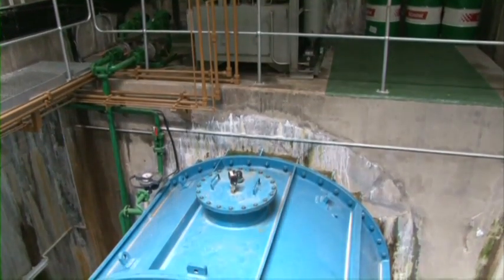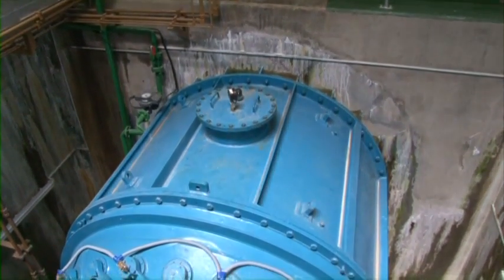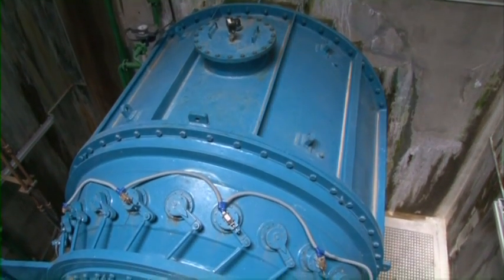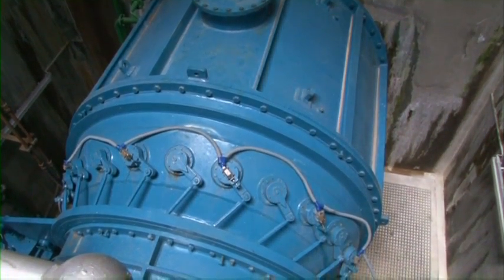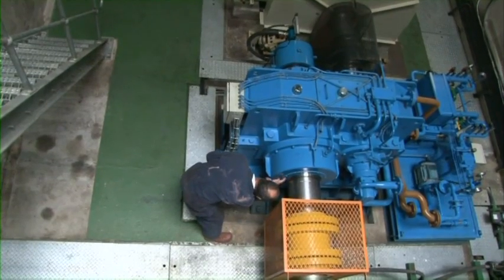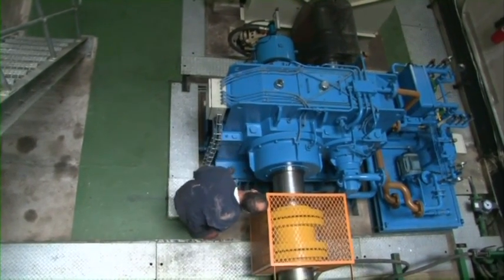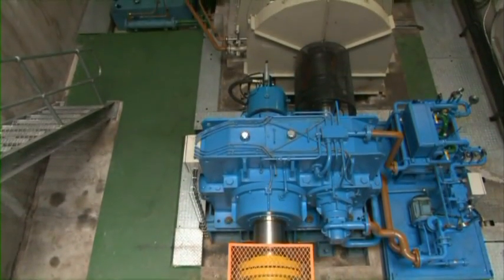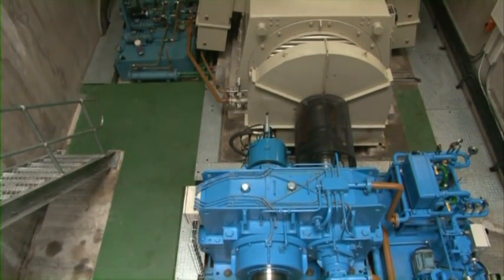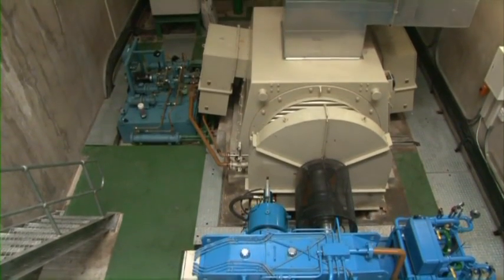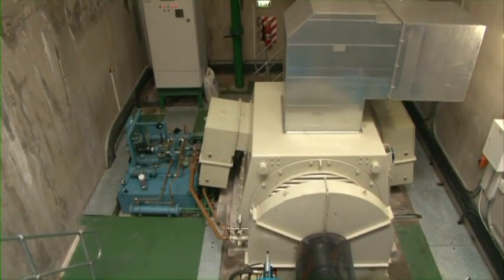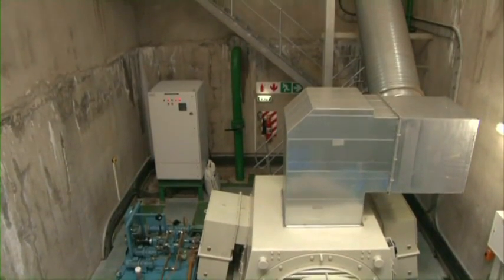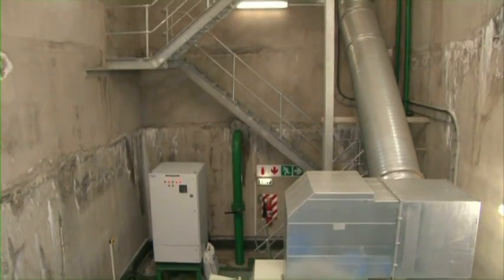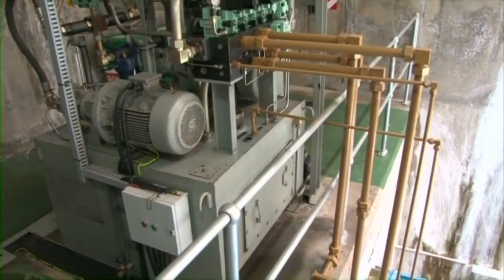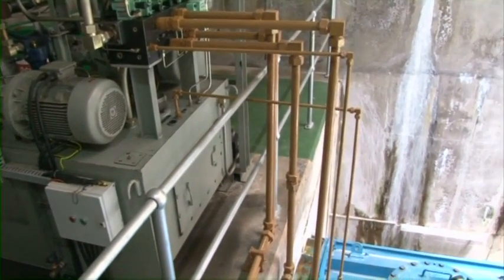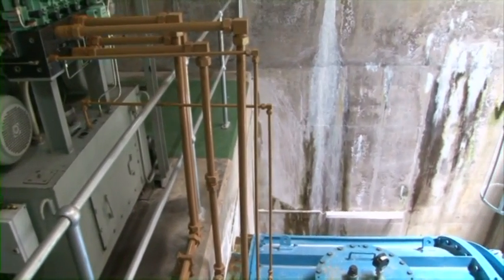The water flows through the intake and into the turbine. The turbine then turns a shaft. The shaft turns at 250 RPM at this point and is stepped up to 750 by the gearbox. The generator then generates at 750 RPM at a voltage of 6.6 kV onto the transformer, which is stepped up to 11 kV. Through this whole process, auxiliary items control the oil temperature and the pressure required for generation. In essence, the turbine oil pressure unit controls how much water is led through the guide vanes onto the runner blades, which is a control of our speed.